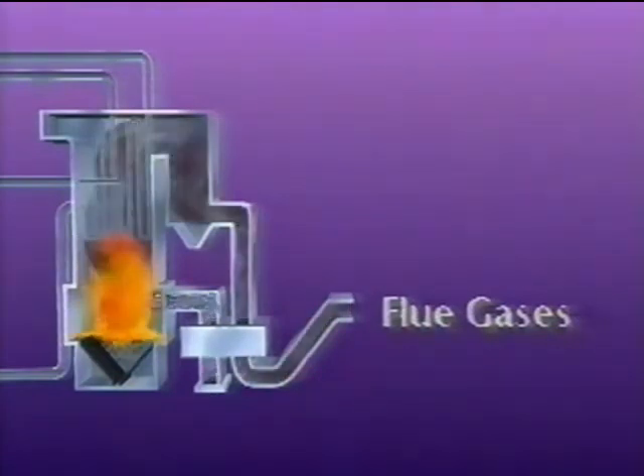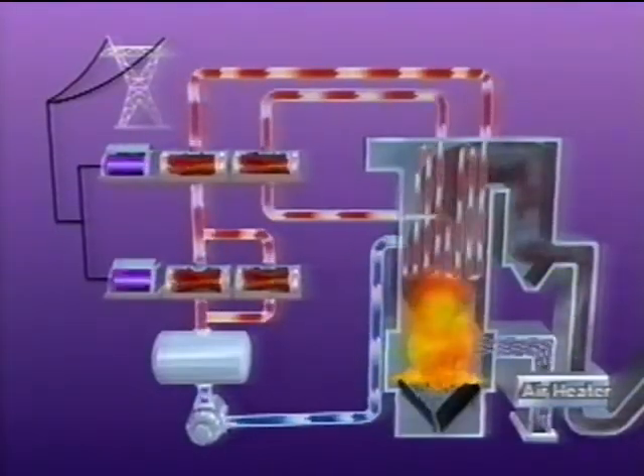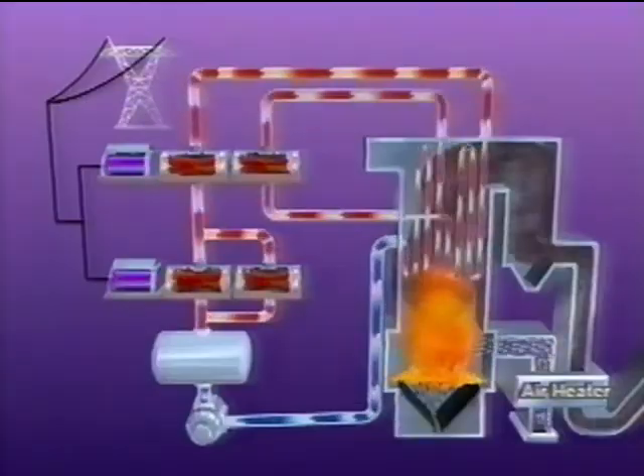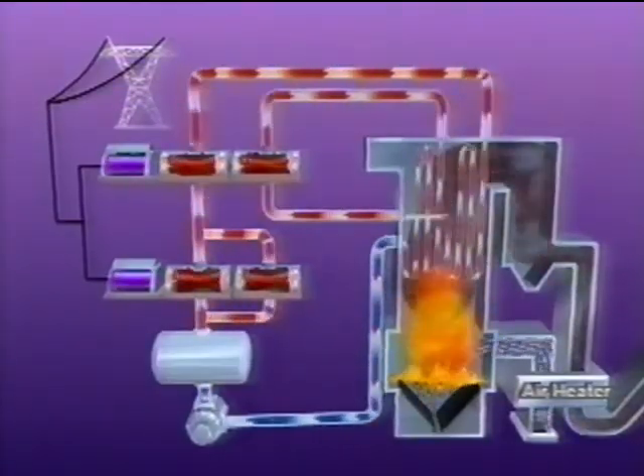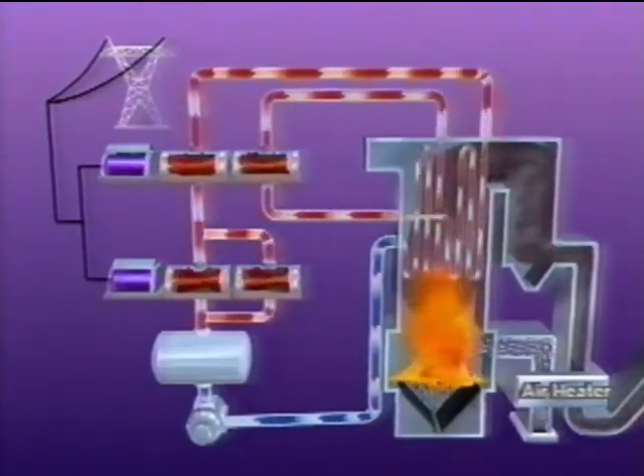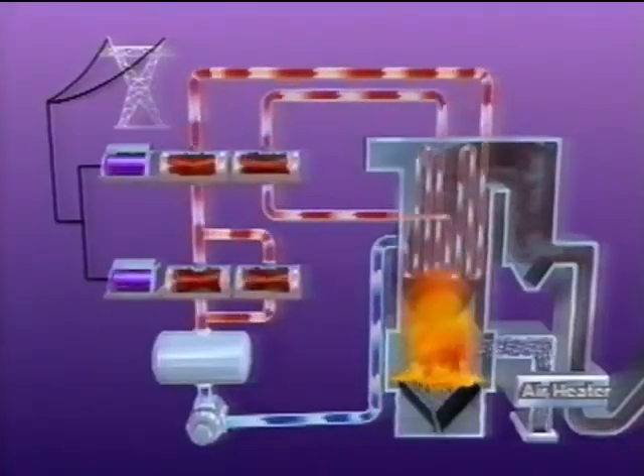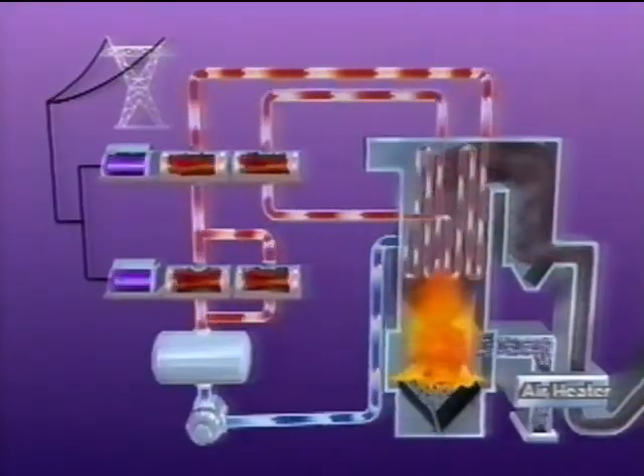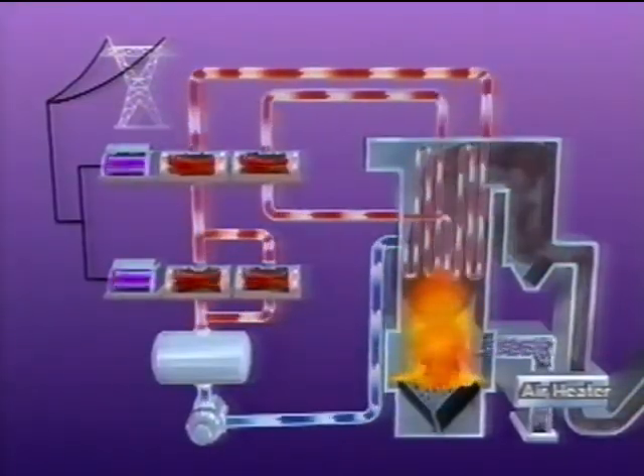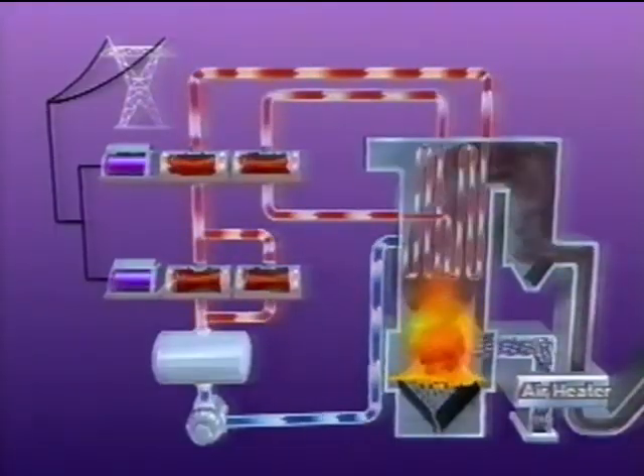Most of the ash, or fly ash, is carried through the furnace by the hot exhaust, or flue gases. The heat from this gas is used in several ways before exiting the stack. It's used to superheat the steam to 1,000 degrees Fahrenheit. It also heats water returning to the furnace and is used to preheat incoming combustion air. All of these uses improve the efficiency of the system.